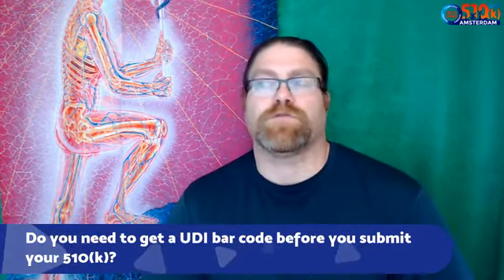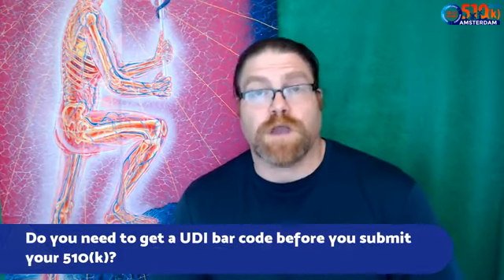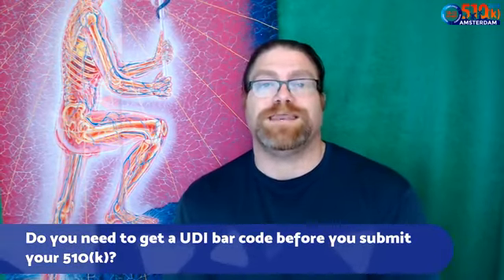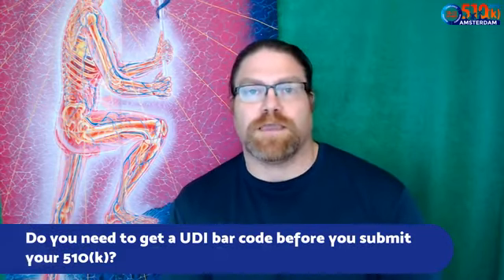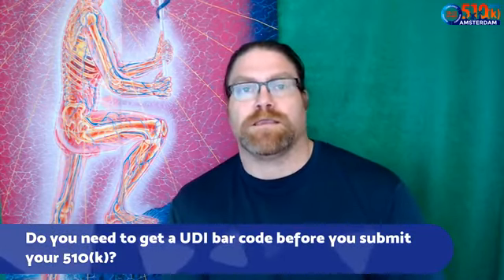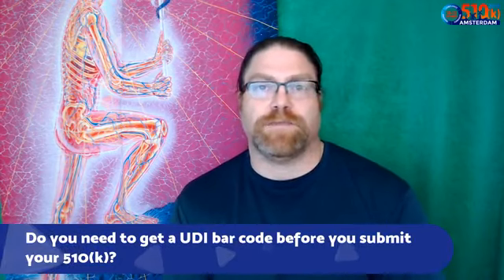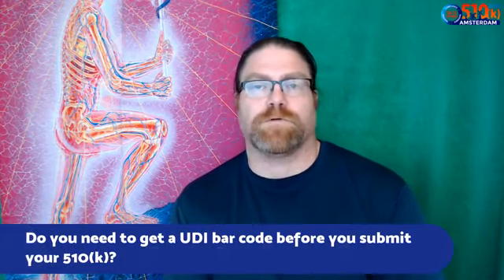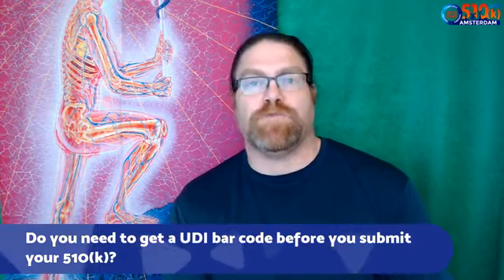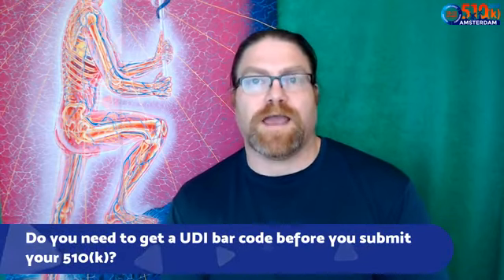One of the other questions I get is, do you need a UDI barcode before you submit your 510K? And the answer is no. In fact, you don't even need it until you actually are putting the product on the market. So you could get your 510K submission in now, get your 510K 90 days from now, or maybe longer, depending on how long the review process takes, and then register the product a year after that.